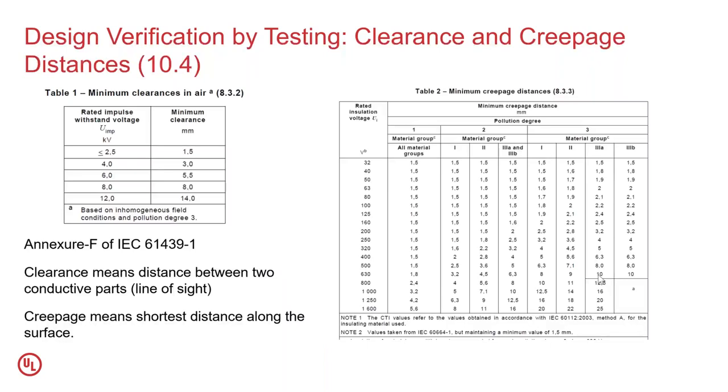Okay, we'll explain in detail further. Understand the concept. For clearance, you require the impulse voltage reference. For creepage, you require the insulation voltage reference. Okay, don't forget that.